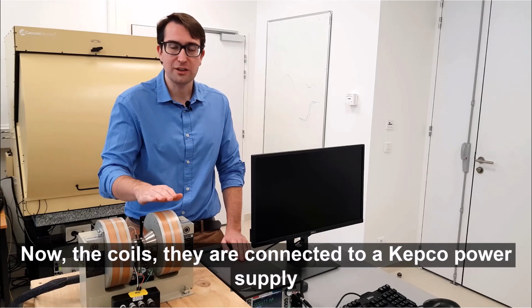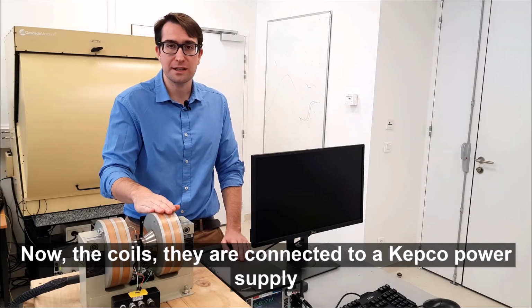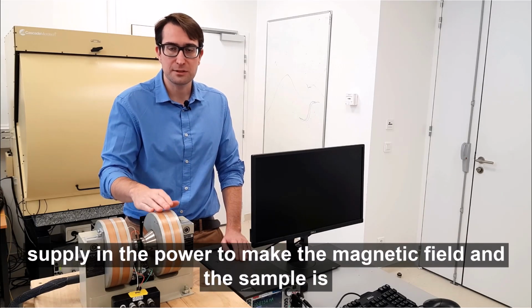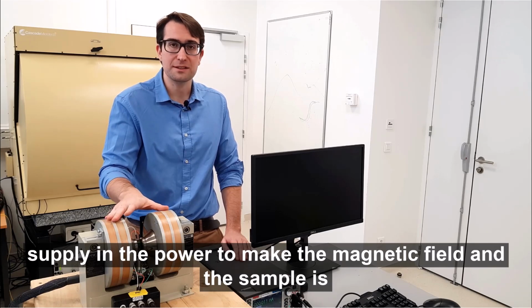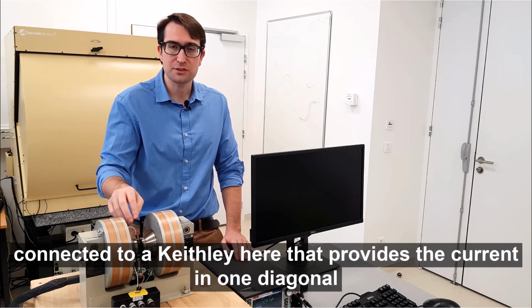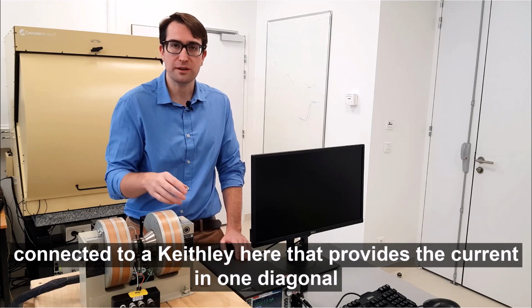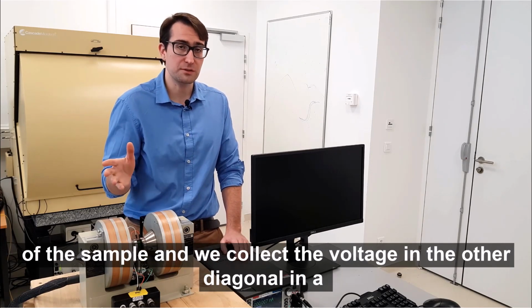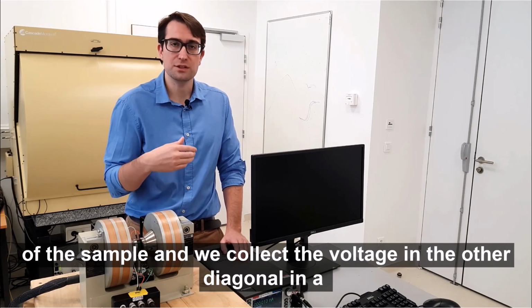Now the coils are connected to a KEPCO power supply that will supply the power to make the magnetic field. And the sample is connected to a Keithley here that provides the current in one diagonal of the sample, and we collect the voltage in the other diagonal.